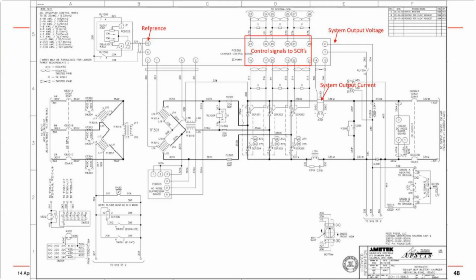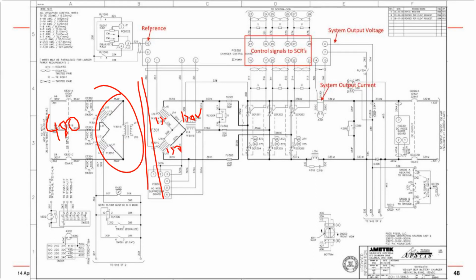Here's a drawing of one of our chargers so you can see it in action. We have our 480 volts coming in through the primary of our transformer, and there's absolutely no electrical connection between the primary and the secondary. Our secondary is where our 130 volt windings are, and then they go through 3 fuses, A phase, B phase, and C phase, and into our SCR bridge. We have 6 SCRs here, and you can see the gate leads go up to our control board.